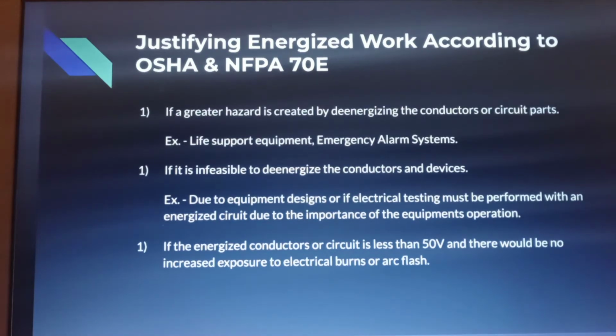And then if it is infeasible to de-energize the conductors and devices, which is due to equipment design, or if electrical testing must be performed with an energized circuit due to the importance of the equipment's operation, like an HVAC system in a chemical processing plant where you need that HVAC system to be filtering the air in there because it could be toxic or something like that. And then lastly is if the energized conductors or circuits are less than 50 volts, and there would be no increased exposure to electrical burns or arc flash. And also, if it's under 50 volts, you don't need to be licensed to work on it anyways.